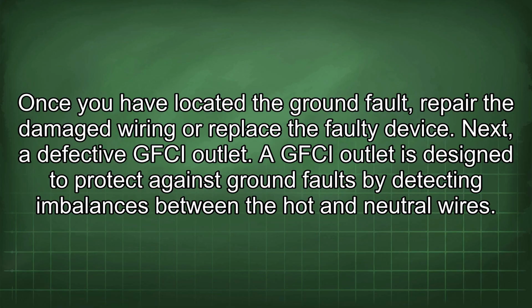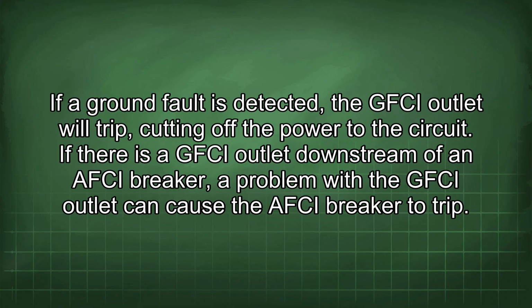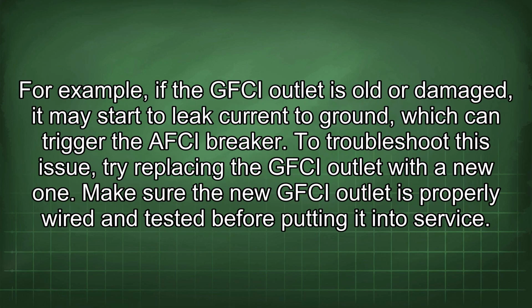Next, a defective GFCI outlet. A GFCI outlet is designed to protect against ground faults by detecting imbalances between the hot and neutral wires. If a ground fault is detected, the GFCI outlet will trip, cutting off the power to the circuit. If there is a GFCI outlet downstream of an AFCI breaker, a problem with the GFCI outlet can cause the AFCI breaker to trip. For example, if the GFCI outlet is old or damaged, it may start to leak current to ground, which can trigger the AFCI breaker. To troubleshoot this issue, try replacing the GFCI outlet with a new one. Make sure the new GFCI outlet is properly wired and tested before putting it into service.